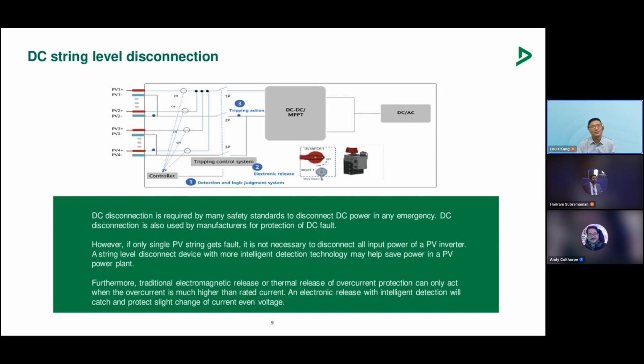A DC disconnection device is used to manually disconnect a PV power plant in an emergency. This device is sometimes also used for automatic disconnection in case of any DC fault. Usually, a DC fault happens only on one string. It will be more efficient if we only disconnect the fault PV string itself rather than the whole DC input of the PV inverter. Such a technique will help save power in a DC fault. Furthermore, traditional electromagnetic release or thermal release of an overcurrent protection device can only act when the overcurrent is much higher than rated current. However, usually even if the PV string is short-circuited, the overcurrent is only 1.1 to 1.2 times the rated current. A traditional disconnection device will not work in such a situation.